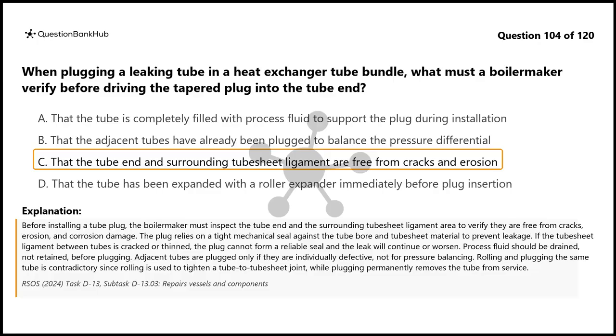Process fluid should be drained, not retained, before plugging. Adjacent tubes are plugged only if they are individually defective, not for pressure balancing. Rolling and plugging the same tube is contradictory since rolling is used to tighten a tube-to-tube sheet joint, while plugging permanently removes the tube from service.